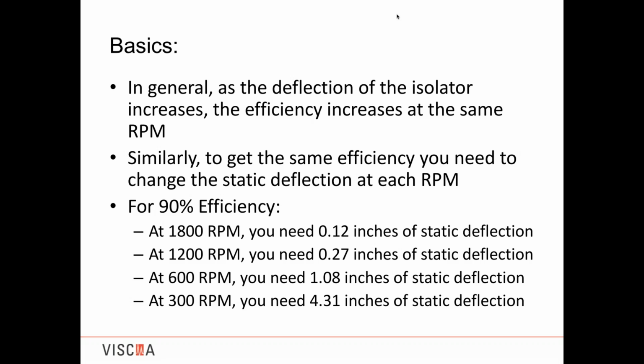And a lot of the newer equipment out there, due to energy efficiency standards and such, will have variable speeds built in. So when you're asking for the RPMs, you may be receiving the highest. You always have to verify that there are no variable speed drives that will bring the motor speed down. Obviously, cooling towers are the big issue with these, if anyone's familiar with those. They have variable speeds down to the order of magnitude of 300 RPMs, and they may have been designed a little faster, and you'll have a system that may only have 1 inch of deflection, and your efficiency drops dramatically.